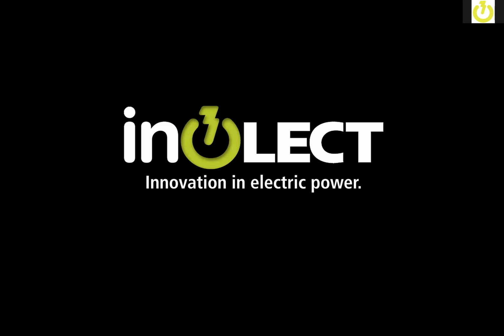Maybe you're trying to implement some remote operation where you push a button on the front of that relay, walk away, and then 10, 20 seconds later, it opens or closes that breaker. You may want to implement communication schemes throughout the facility so you can open and close breakers and see relay status from across your plant without having to leave your office or the operator control room.